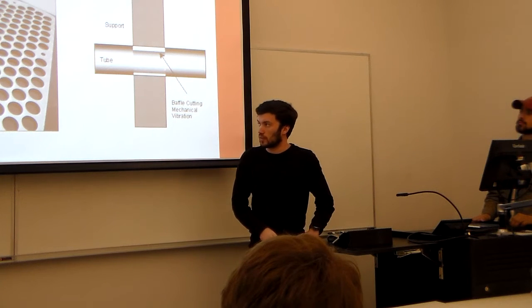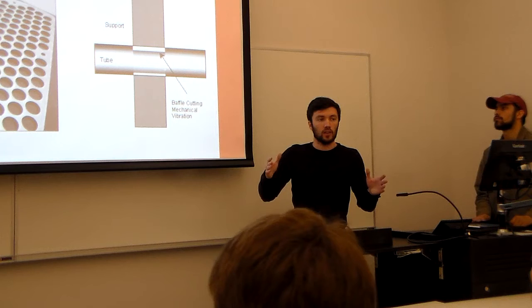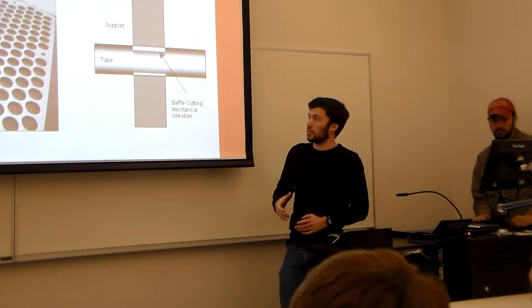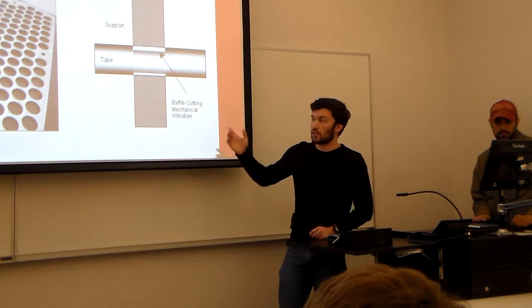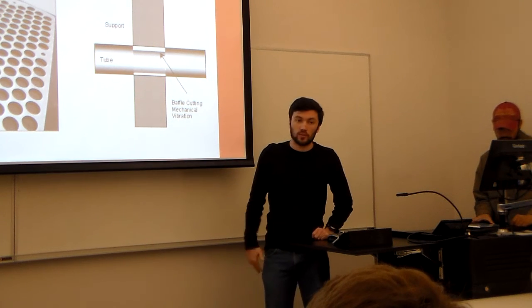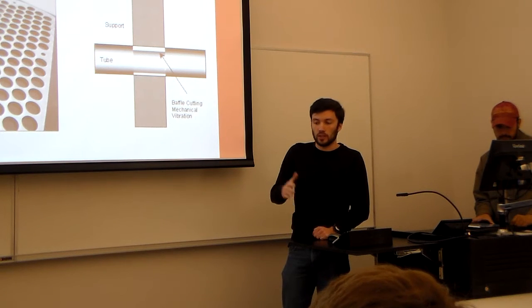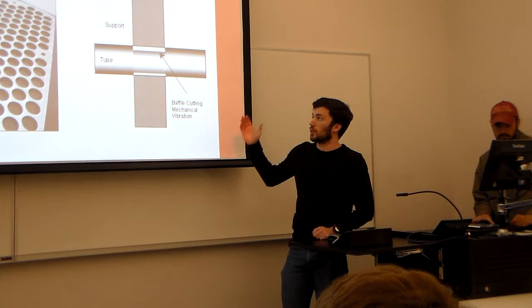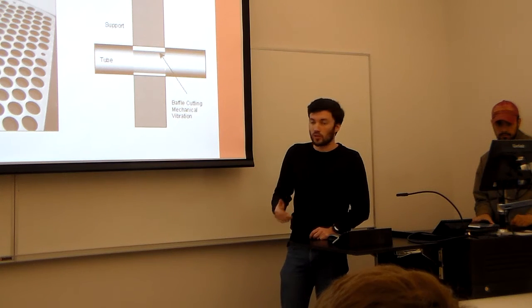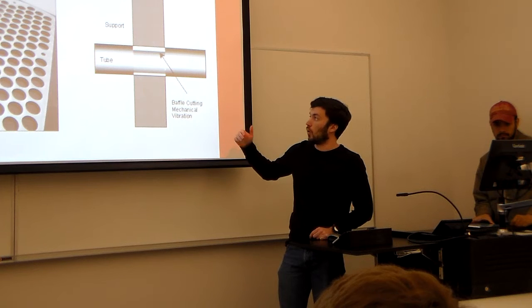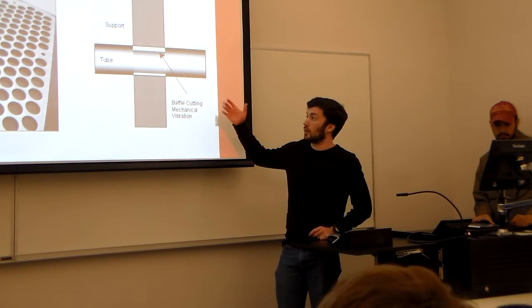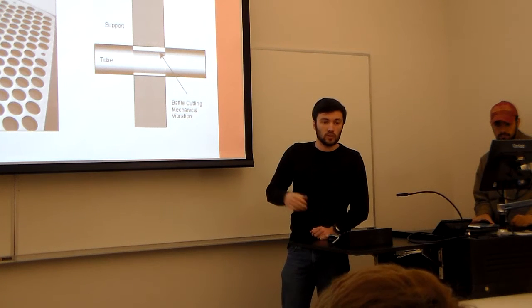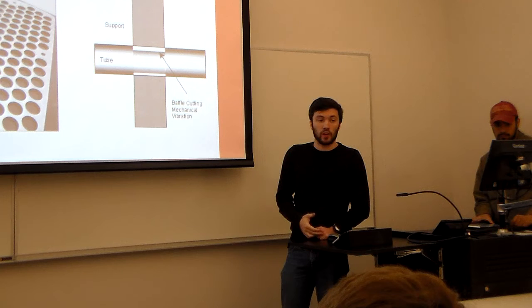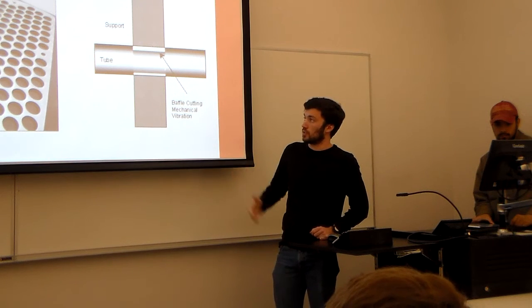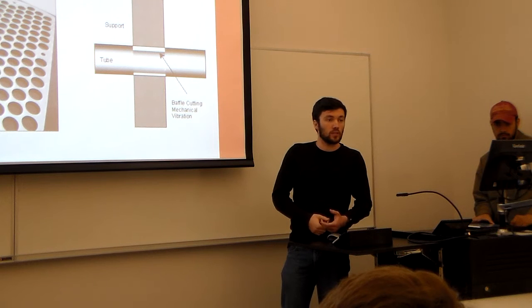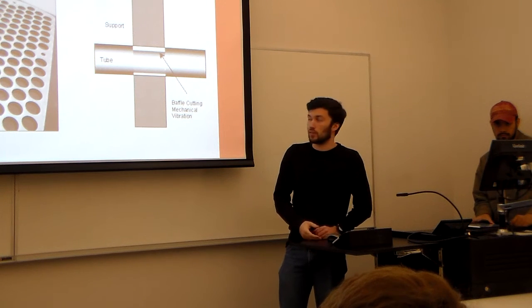So one of the biggest issues with the design of these heat exchangers is, like I said before, that the end caps are welded, but because of the constraints of trying to weld each of these to the baffles, they're not. There's actually a clearance between these tubes and the support baffles. And because there's space there, that leaves room for wear and tear from vibration because of the high pressure that runs through these systems. So eventually, over time, these baffles will begin to eat away the wall of the tube, and the baffles themselves will actually have some degradation also. Eventually, this will cause the tubes to fail. And then instead of having a closed system where the hot and cold liquids don't meet, they're now mixing. And that really affects the overall efficiency of the heat exchanger.